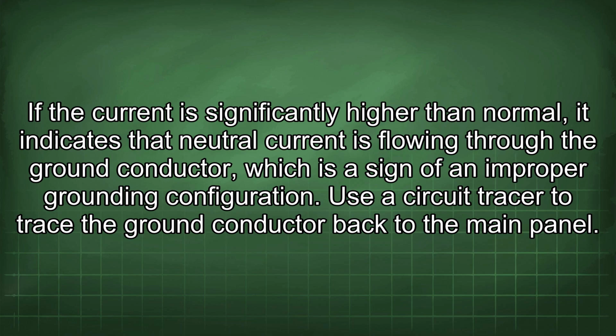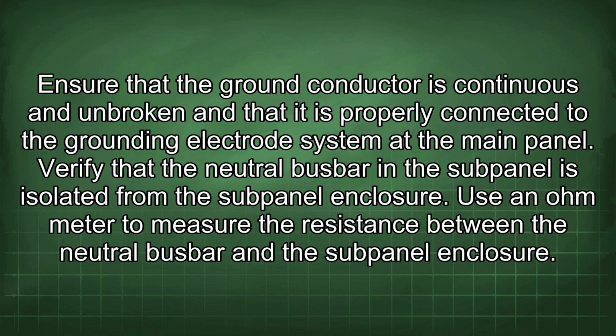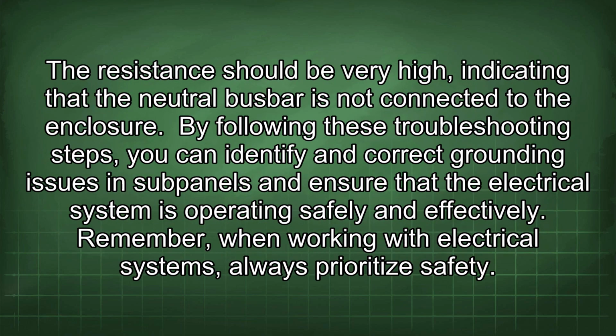Use a circuit tracer to trace the ground conductor back to the main panel. Ensure that the ground conductor is continuous and unbroken and that it is properly connected to the grounding electrode system at the main panel. Verify that the neutral busbar in the subpanel is isolated from the subpanel enclosure. Use an ohmmeter to measure the resistance between the neutral busbar and the subpanel enclosure. The resistance should be very high, indicating that the neutral busbar is not connected to the enclosure. By following these troubleshooting steps, you can identify and correct grounding issues in subpanels and ensure that the electrical system is operating safely and effectively.